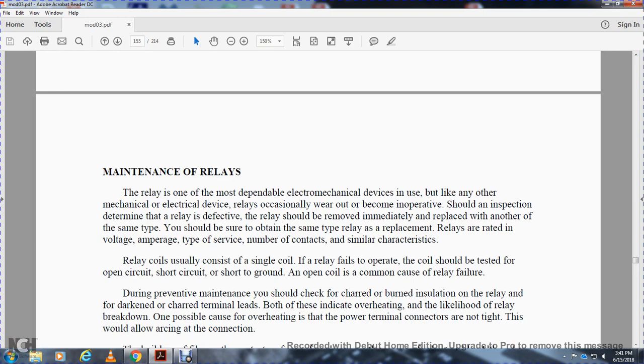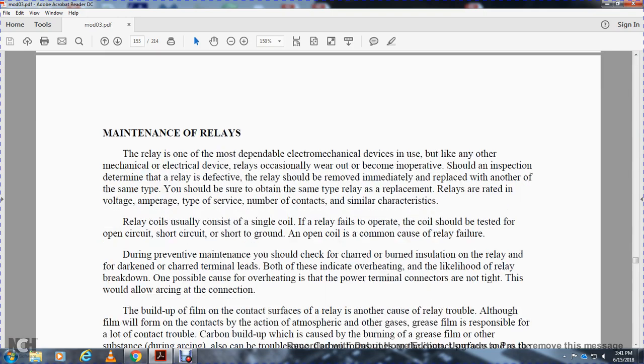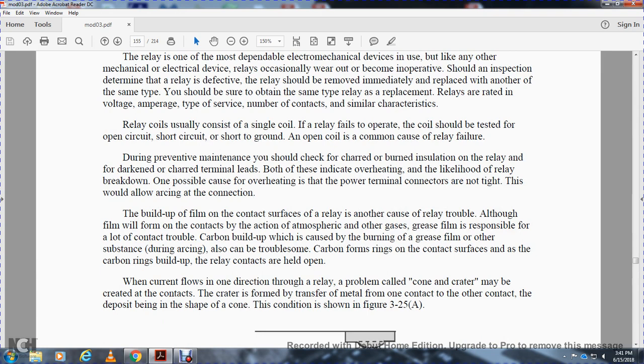Replacement relays are rated in voltage, the amperage, the type of circuit, the number of contacts, and similar characteristics. Relay coils may be used, consisting of a single coil. With a relay failure to operate, the coil should be checked for an open circuit, a short circuit, a short to ground, or an open coil. During preventive maintenance, you should check for charred or burnt insulation on the relay and discolored or charred terminal leads, both indicating overheating and the likelihood of relay breakdown.